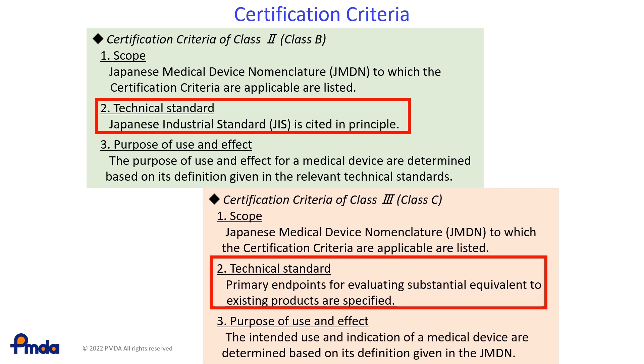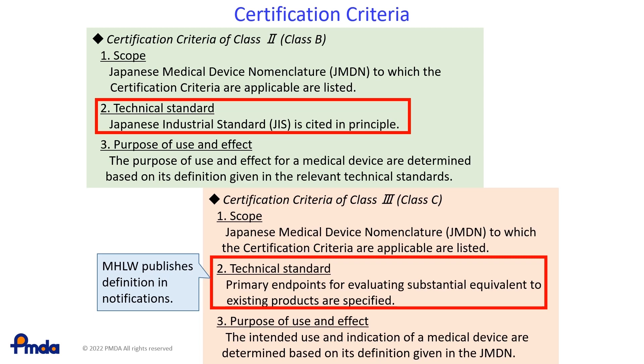Primary endpoints for evaluation of Class II are mostly cited in JIS and IEC. Whereas for Class III, the method of evaluation for primary endpoints using JIS, ISO and/or IEC is defined in Notifications published by MHLW.